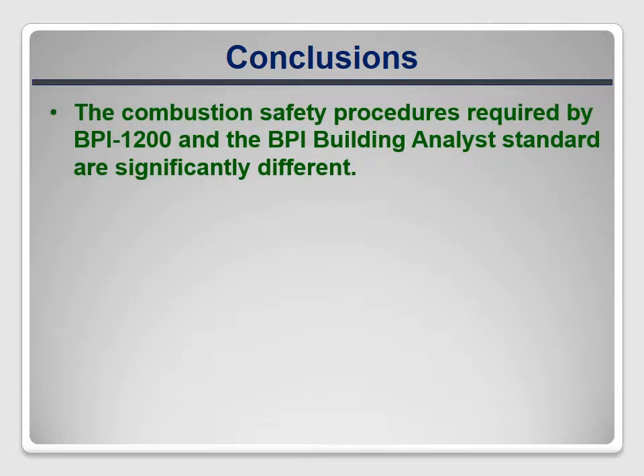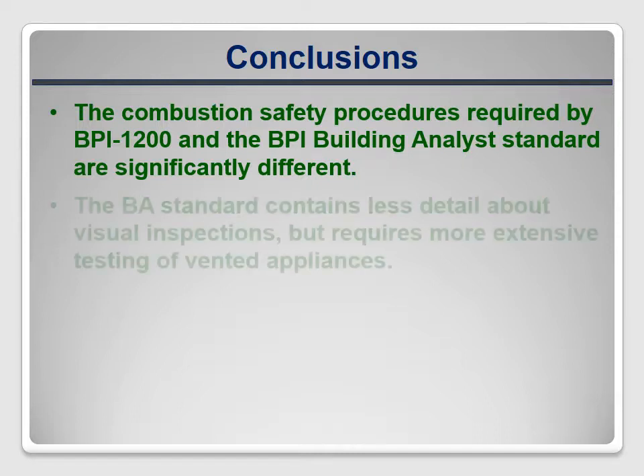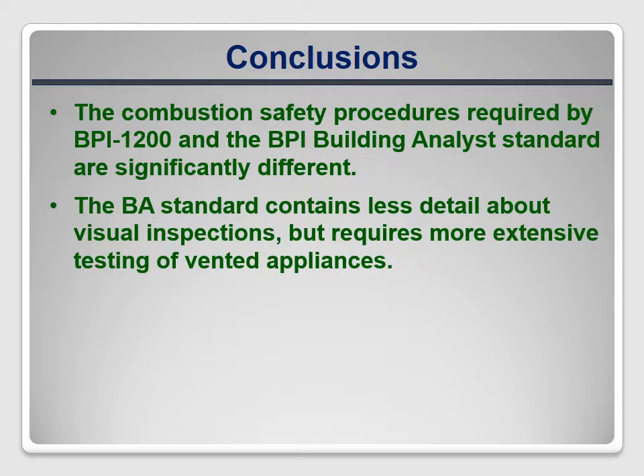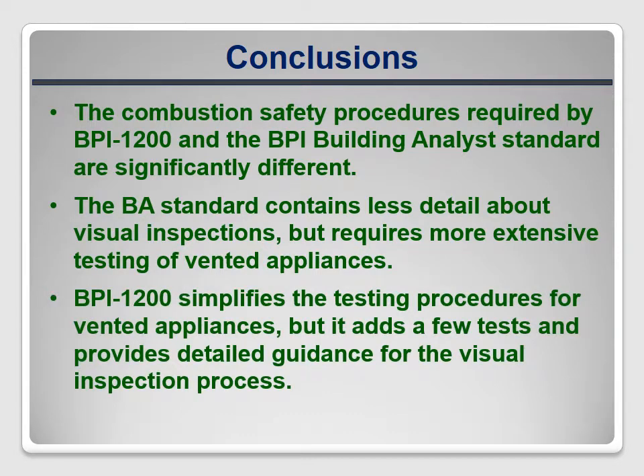Based on this review, it's clear that there are significant differences in the combustion safety evaluation procedures in BPI 1200 and the Building Analyst Standard. In general, the Building Analyst Standard contains less detail, especially regarding visual inspection procedures. However, the BA Standard requires more extensive testing of vented combustion appliances. The testing procedures in BPI 1200 are more streamlined — several steps are eliminated — but this newer standard adds some new testing and provides more detailed guidance to auditors about conducting visual inspections.